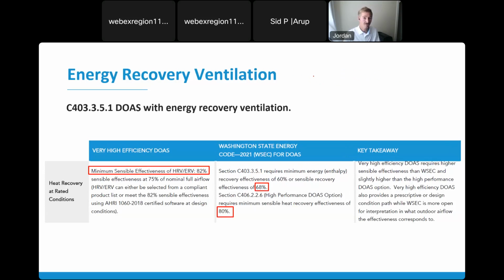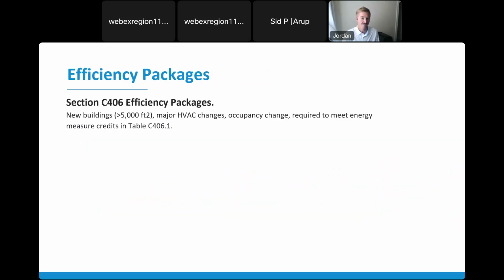Next section is energy recovery ventilation, which is required in those building types. Very high efficiency DOAS, as I mentioned, recommends 82% sensible effectiveness. Washington State Energy Code, as of 2021, now requires 60% total enthalpy or 68% sensible. So a little bit lower than the VHE DOAS, but in the energy efficiency credits section, which is also required in new construction and major retrofits, I'll get into that in a little more detail, it has 80% for the high performance DOAS option. So very similar for the advanced energy package.